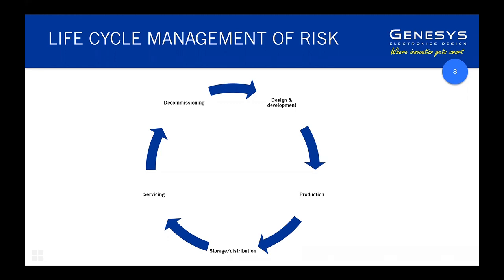And this is where we get into the slightly slippery slope domain of technical reports, which in fact do not define an imperative that you must follow, but you'll find the FDA, for example, tend to place a lot of credence on the technical reports that give guidance to the risk management process, and one would be foolish not to follow that.